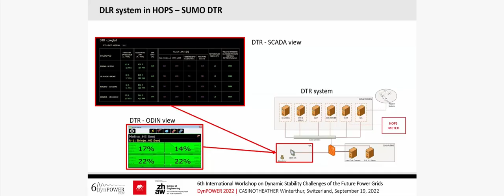Just some details about the two other systems mentioned in the project. They are sensor-based, so the sensor is installed for the OTLM system on the line. Here we have two, but one is enough. This was one project where we wanted to look at the loadings on the tower with two sensors, because this sensor also measures the angle of the line. But for this DTR system, it's okay to have only one.